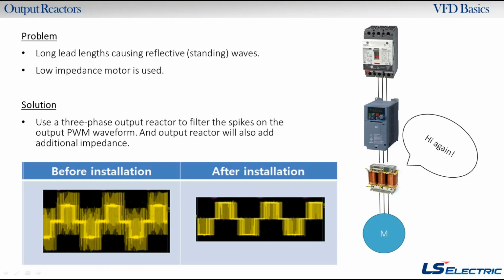Or if you have a low impedance motor, like these Baldor Super E's or NEMA design A motors, which are very highly efficient low impedance motors, adding that additional impedance is going to help you out in a few ways. It's going to reduce the reflective or standing waves. We already have a high voltage waveform going out to the motor. The motor can handle it, but when you extend the distance from the drive to the motor, the cable kind of acts like an amplifier, and that cranks up the voltage more.